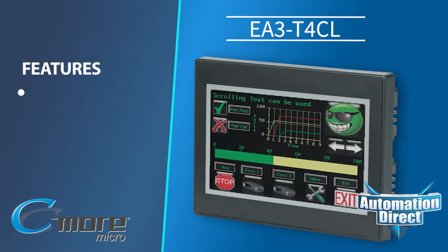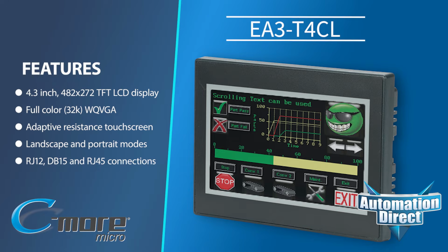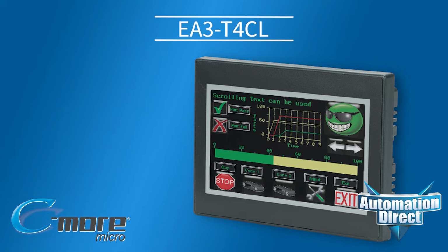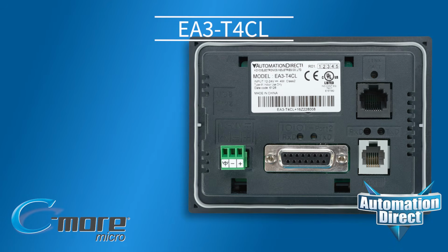Now, let's look at the T4CL model, the larger, full-color option in the C-more Micro family. This model offers a 4.3-inch 482 by 272 full-color touchscreen display. Supporting both landscape and portrait modes, this panel has a palette of 32,000 colors for customizing objects, screen backgrounds, and displaying bitmap graphics. With the same connection ports as the S3ML model, it also supports all the same protocols.